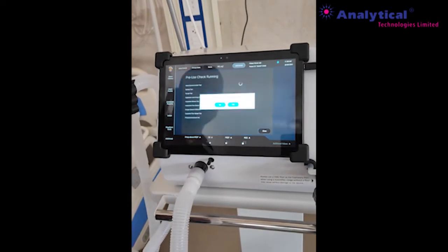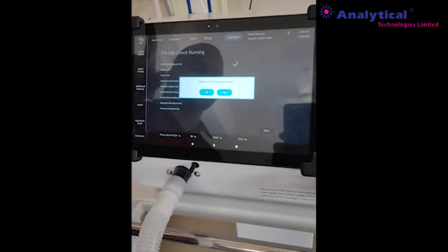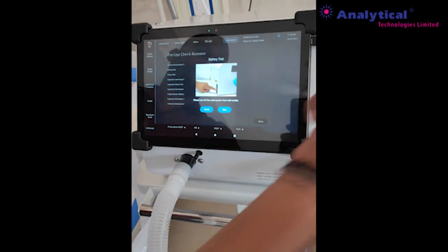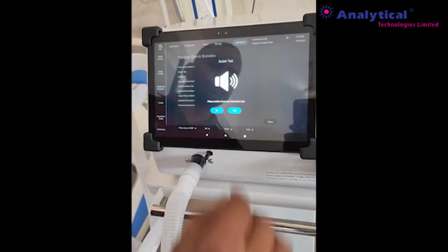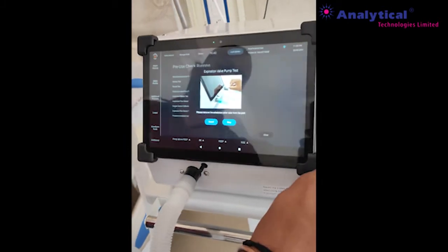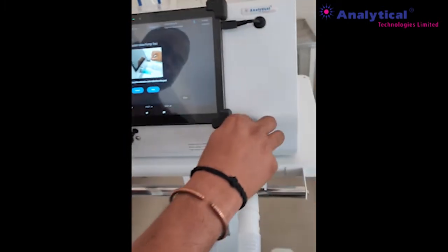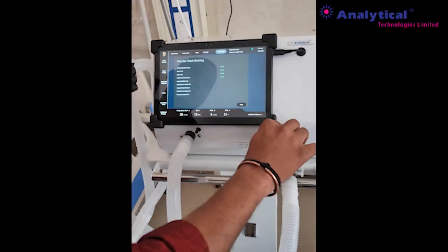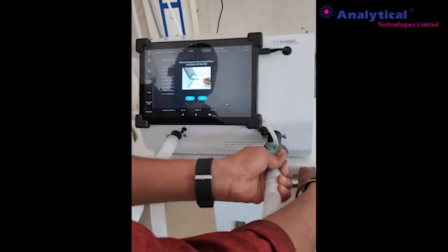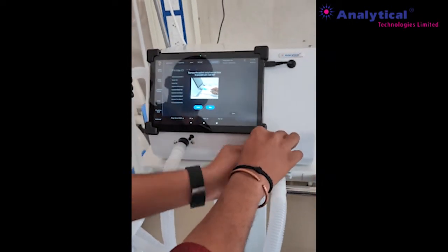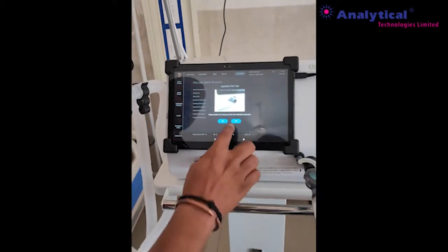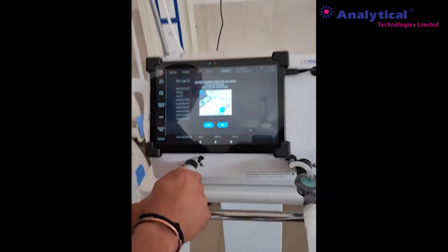So before you give the connection to the patient, first do a pre-check. So switch off the oxygen supply at the back side. Yes. After that, power connection, switch on. Alarm, buzzer. So remove this one, expiratory. So okay. After that, yes. Remove inspiratory. Yes. So fit again. Okay.